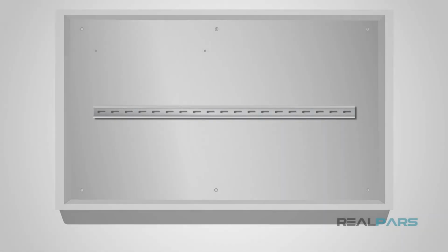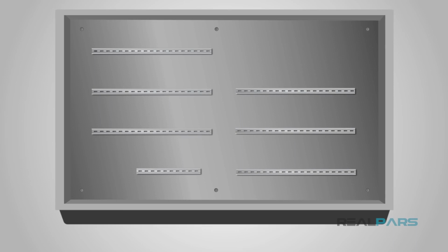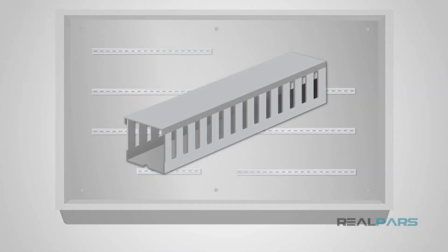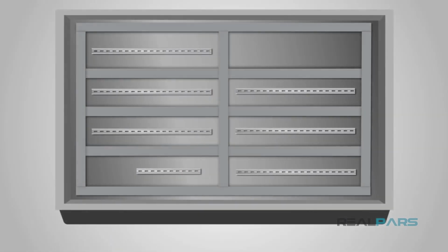Now, let's go inside the enclosure and talk about the non-electrical components that make up the control panel. First, let's talk about the back panel of the enclosure. The back panel is a sheet of metal that is mounted on the inside of the enclosure that allows us to drill mounting holes for different devices, which leads us to our next component, DIN rails. A DIN rail is a metal rail with a standard width used for mounting electrical devices inside. The next component inside the control panel is wiring duct. Ducts allow us to route the wires in an organized and efficient way, while also reducing electrical noise between devices.